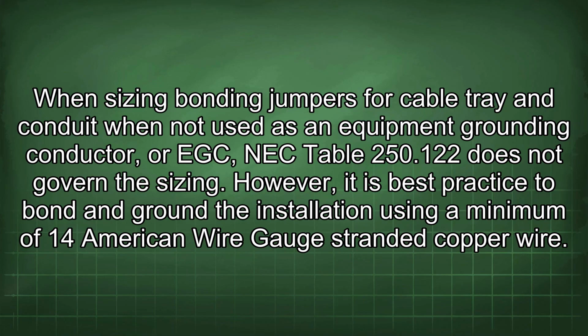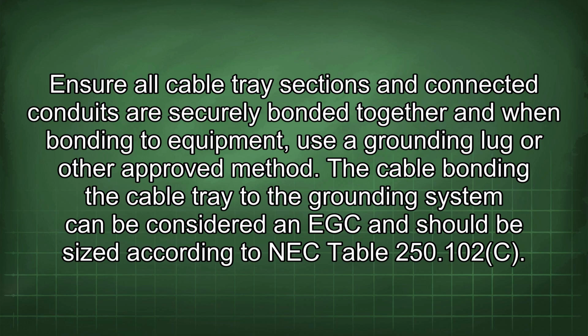When sizing bonding jumpers for cable tray and conduit not used as an equipment grounding conductor, or EGC, NEC Table 250.122 does not govern the sizing. However, it is best practice to bond and ground the installation using a minimum of 14 American wire gauge stranded copper wire. Ensure all cable tray sections and connected conduits are securely bonded together, and when bonding to equipment, use a grounding lug or other approved method.